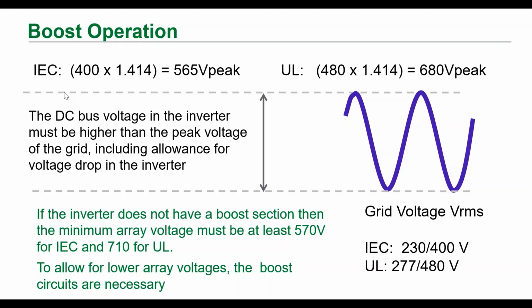For Asian and European countries, we adopt a 400 volt AC system, so your boost voltage should be greater than or equal to 565 volt. How do we calculate this 565? 400 volt is the RMS voltage of the AC system, and you calculate the maximum voltage as √2 times Vmax into VRMS - so 400 is VRMS, and times √2 gives you peak voltage. Your DC link voltage should be greater than or equal to the maximum voltage of your AC system, then only the inverter will be stable. Otherwise there will be reverse flow, feedback from grid to system - that's when someone mentions negative flow in a microgrid. This type of thing happens when you design it wrong. So your DC link should always be maintained greater than or equal to the peak voltage of your AC system.